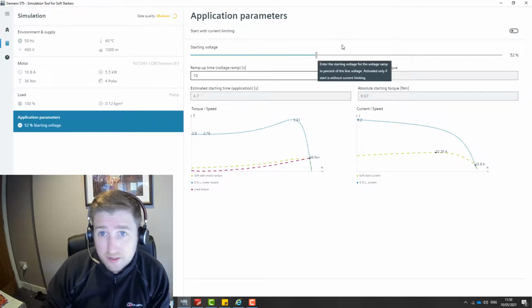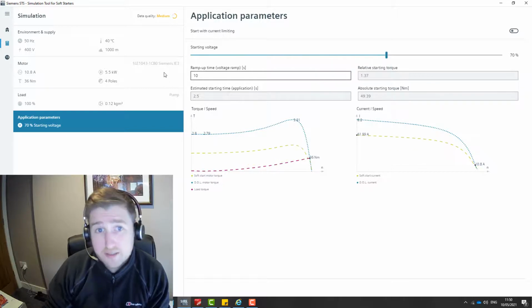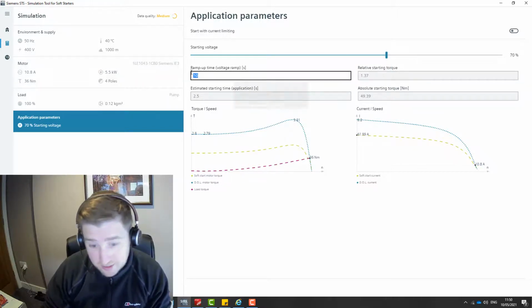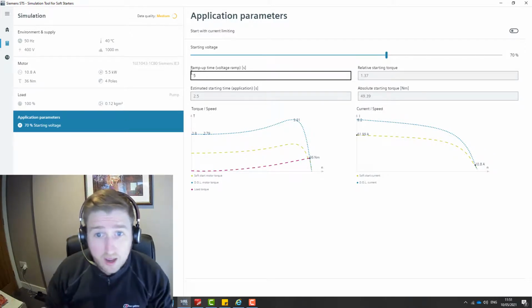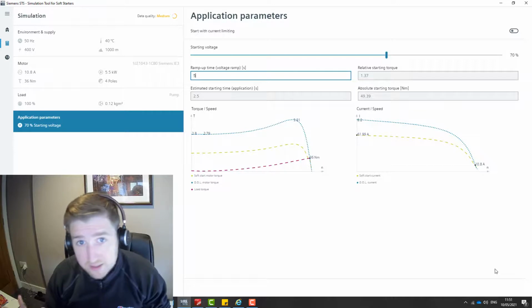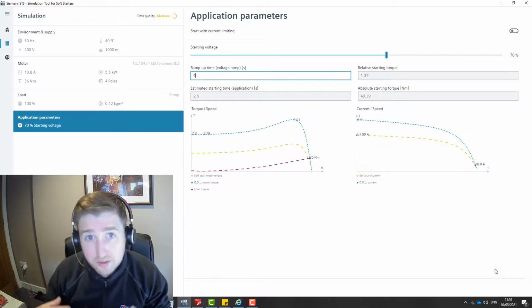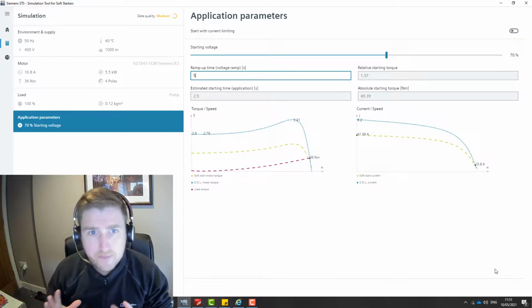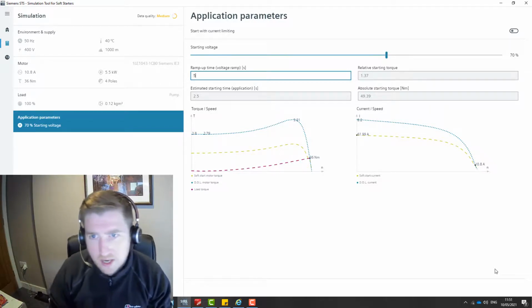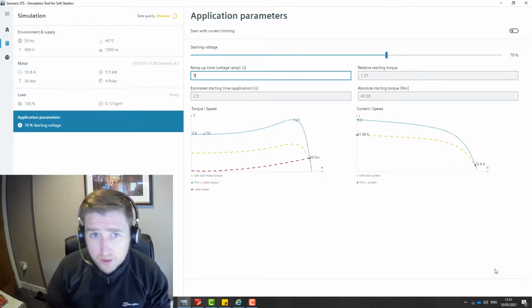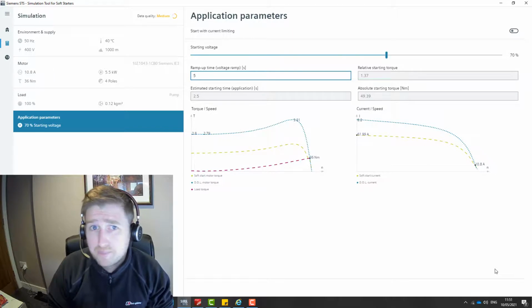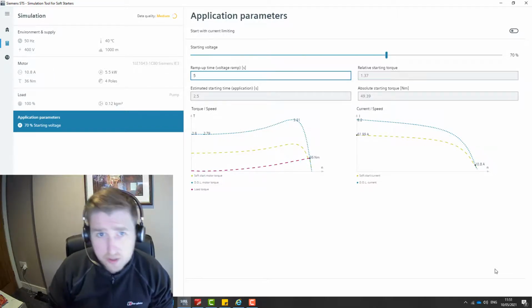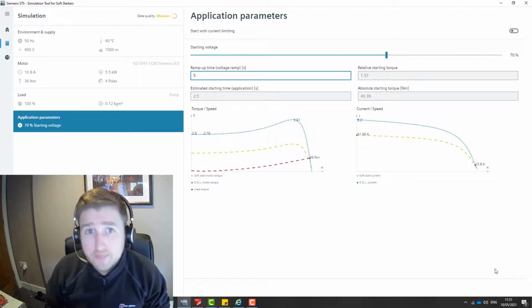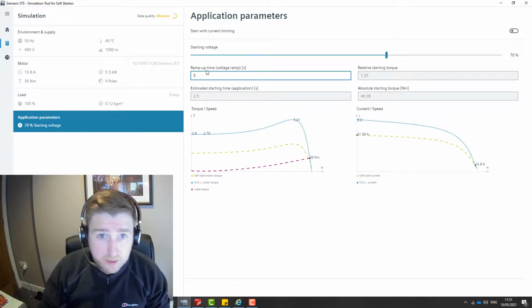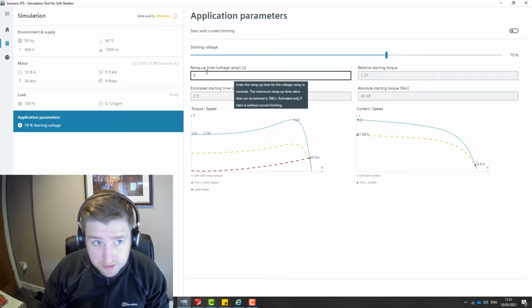So we can rest assured knowing that if we set this starting voltage parameter to 70%, and then we change the ramp up time here from 10 seconds to say 5 seconds, we've had no message in this bottom right hand corner to say that the motor isn't going to start. Those parameters are sufficient to get the motor started. We now know what the starting current needs to be for the current limiting function. We also know what the starting voltage needs to be for this application, and that the ramp up time can be suitably selected for 5 seconds.